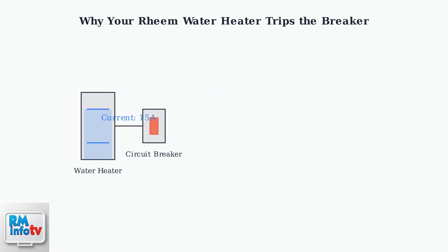The most common cause is a burnt or damaged heating element. When an element fails, its electrical resistance decreases, causing excessive current draw that trips the breaker.